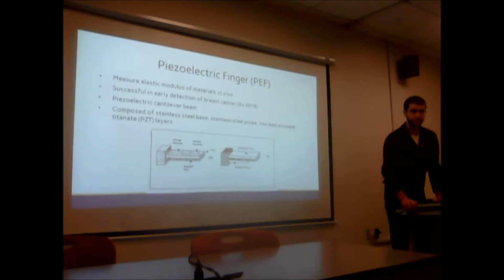So the way a piezoelectric finger, or a PEF, works is that it measures the elastic modulus of tissues in vivo. And the way that it is able to do this is by having 3 layers, 2 made out of lead zirconate titanate, or PZT, and then a stainless steel layer. A voltage is applied on the top PZT layer, which causes the cantilever bar to bend.